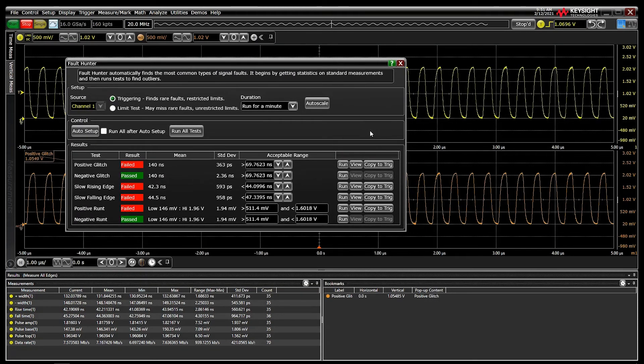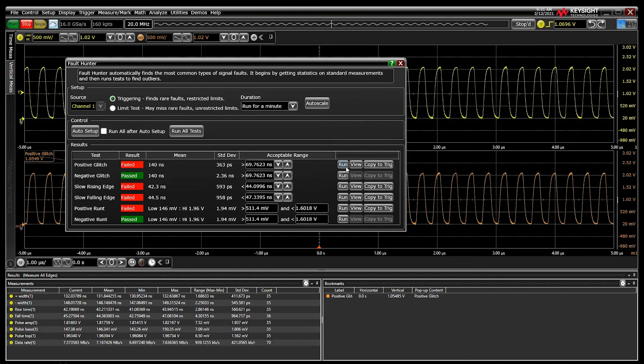Once an error is found, a copy of the error is saved into memory with a timestamp, and Fault Hunter moves on to the next test.